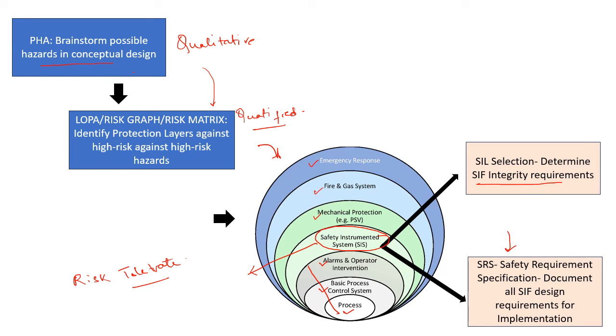Then comes the SRS where much more detail of the SIL requirement is specified. It includes your SIL requirement, the design, how it should be designed. There are inputs like the process safety time, which means how fast the safety instrumented function needs to respond to a demand. During the LOPA and after the LOPA you identify the different protection layers and also at the same time you identify how much risk reduction is required through the safety instrumented system.